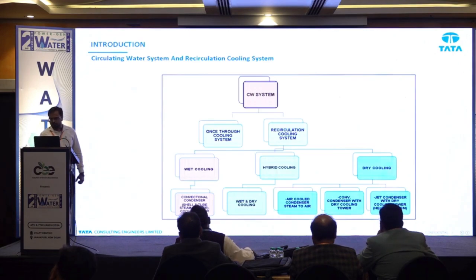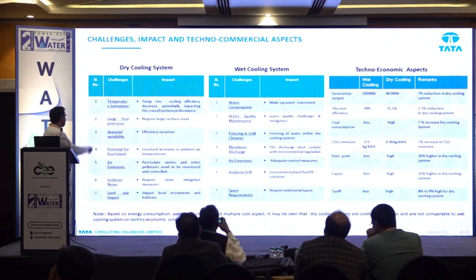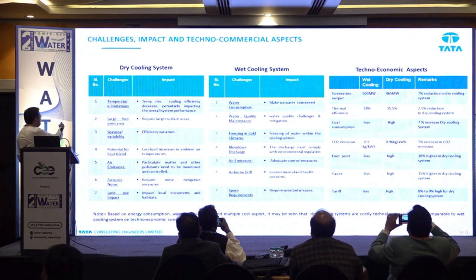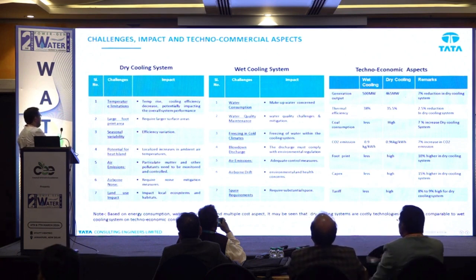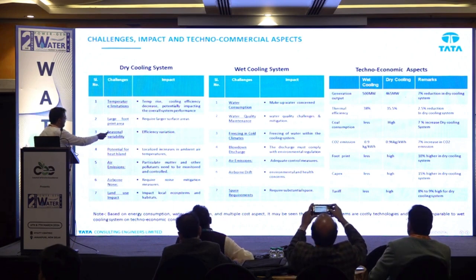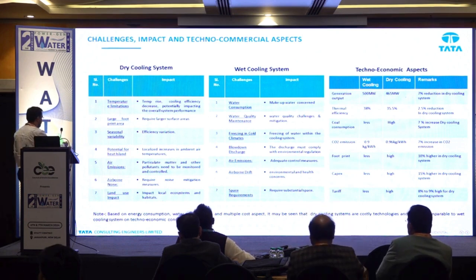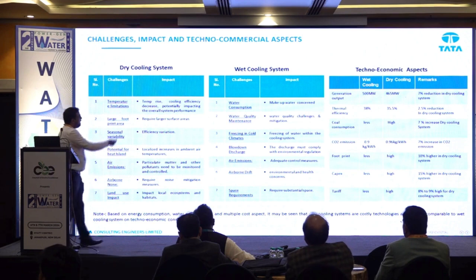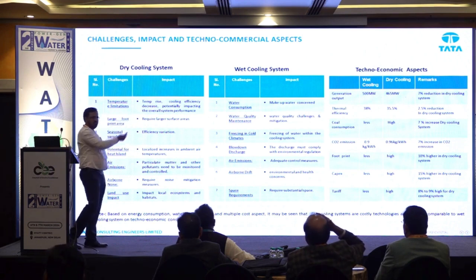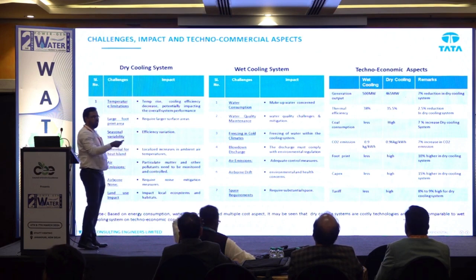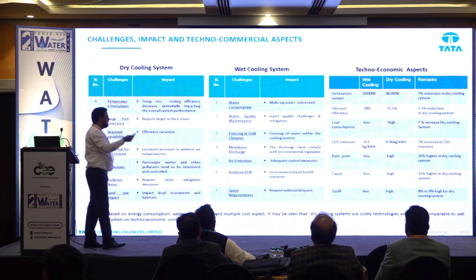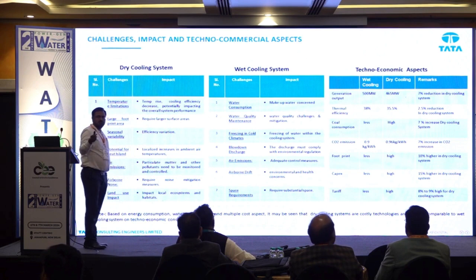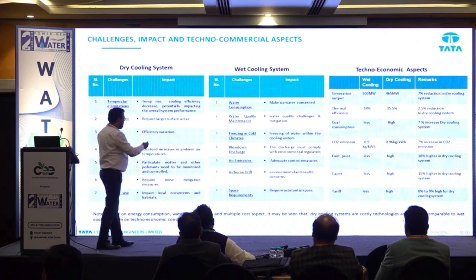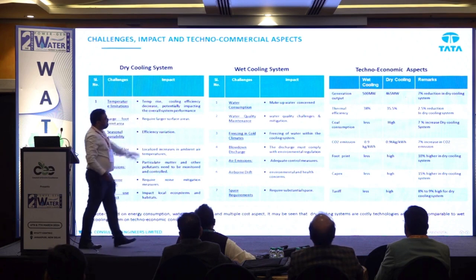Now if we go to the wet condition, I am just making a comparison. For the dry cooling system, the limitations are large footprint area, seasonal variability, efficiency variation, potential for heat island effect, increase in the ambient temperature because of air heat, air emission, airborne and land use impact. On the other side, wet cooling has challenges too, like water consumption. As I told, makeup water has to be of very high quality. We have to maintain it based on the LSI, plus 2 or minus 2, or 0.5. That treatment part our previous dignitaries have already explained.